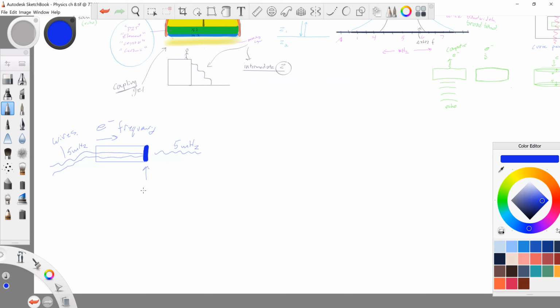There is, of course, every element has a happy place. And that's where it rings. That's where it wants to ring. So it's going to have a fundamental frequency. So, pulse wave transducers. A pulse wave ultrasound system creates short duration electrical spikes that travel through the wire and strike the PZT crystal in the transducer. This produces a process similar to just quickly striking the key of a piano. When the key is depressed, a small hammer.